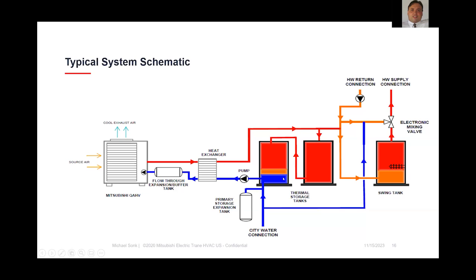Now, with heat pump water heaters, typically because of economy of scale and upfront cost, and the fact that they're optimized for running at full peak capacity and then shutting off, you want to minimize the number of cycles per day, because cycling is not good for the longevity of the equipment. You're dealing with typically very low charge rates, or in other words, lower generation rates and much higher storage volumes than what you're conventionally used to seeing in typical domestic hot water systems.